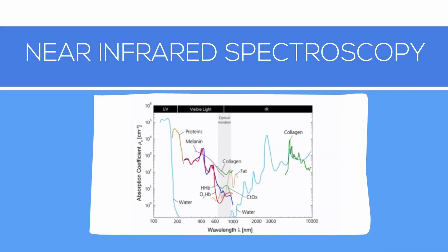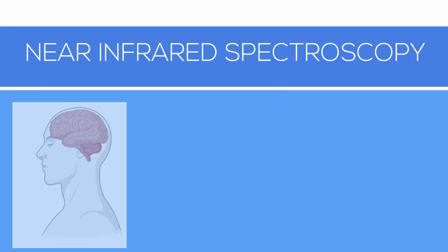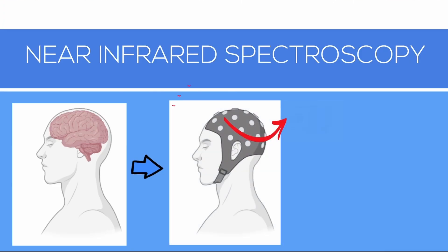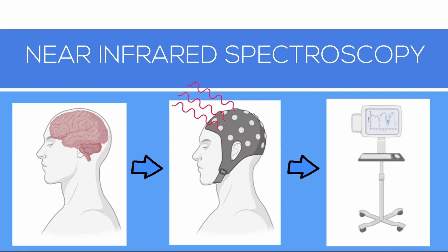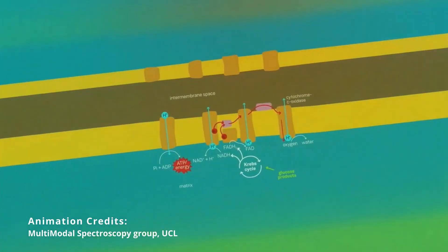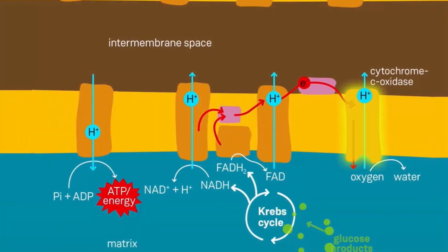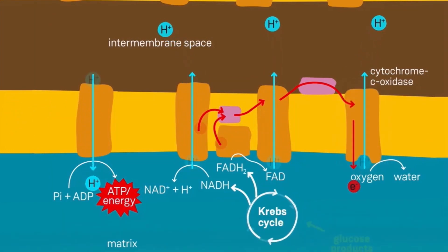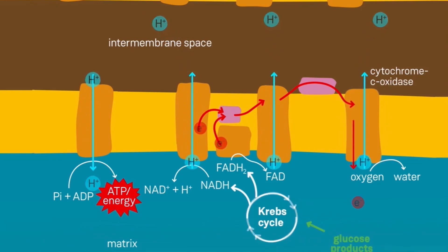Can you tell us a little bit more about the principle of near-infrared spectroscopy? Near-infrared spectroscopy works by shining infrared light, which is in the range of about 650 to 1000 nanometers, into the head. This gets about three centimeters deep, goes in a parabola shape, and is picked up by a detector on the surface. You can use the change in intensity to work out the concentration of chromophores in the brain—chromophore just means it changes color when it interacts with light.